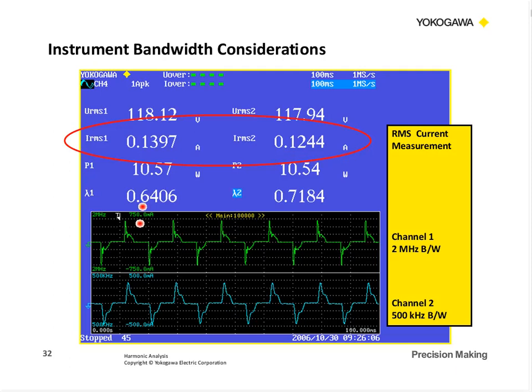Big difference here when we calculate the power factor. So you can see what happens. We've got to take the instrument bandwidth into consideration when we're dealing with distorted waveforms in order to get all the harmonics. So using a different type of instrument can result in different types of measurements.